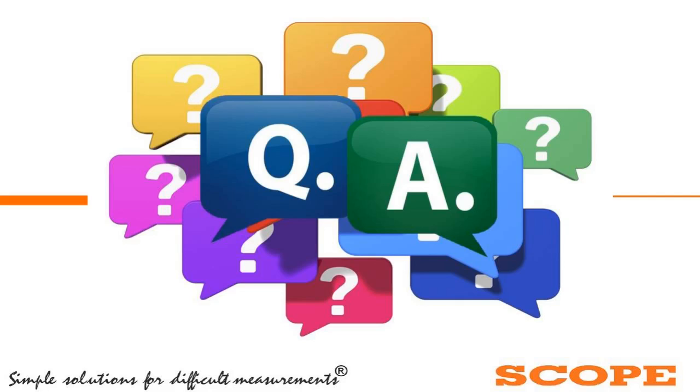So let me again put this point to you guys, that even earlier I told you that there is a confusion in terms of measuring partial discharge in terms of pC or in other units. And then this second question arises: whichever way you are measuring it, what is the safe value? Now, the answer that was given by one gentleman was that it is less than 5 pC in terms of GISs.